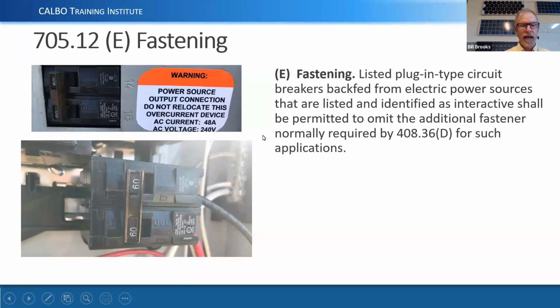Here's an example of fastening. We're not required to fasten plug-in breakers when we're connected to the interactive output of an inverter. The interactive output of the inverter is the one that interacts with the utility. If it ever loses utility, then it automatically shuts down, and so there's no need. If that breaker were to come loose, it'll just shut the inverter off and no damage will be done.